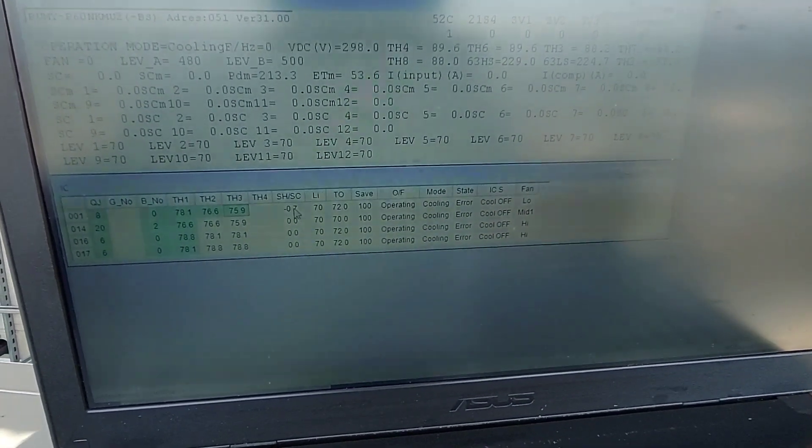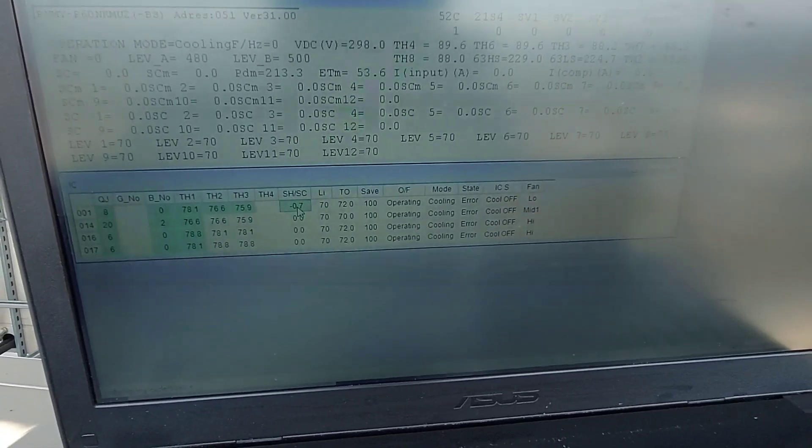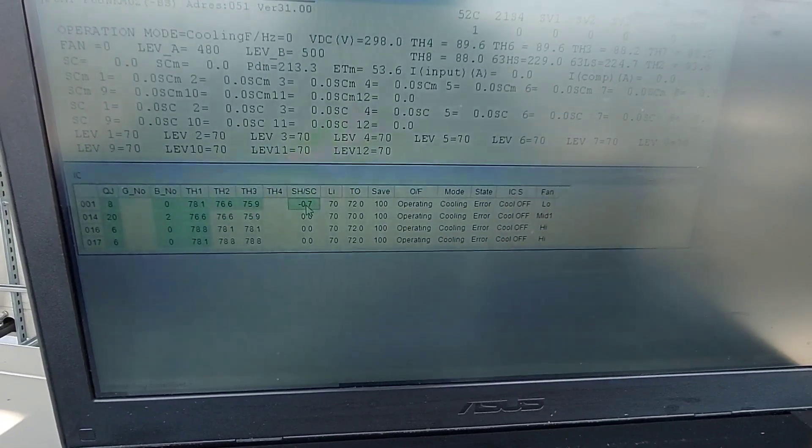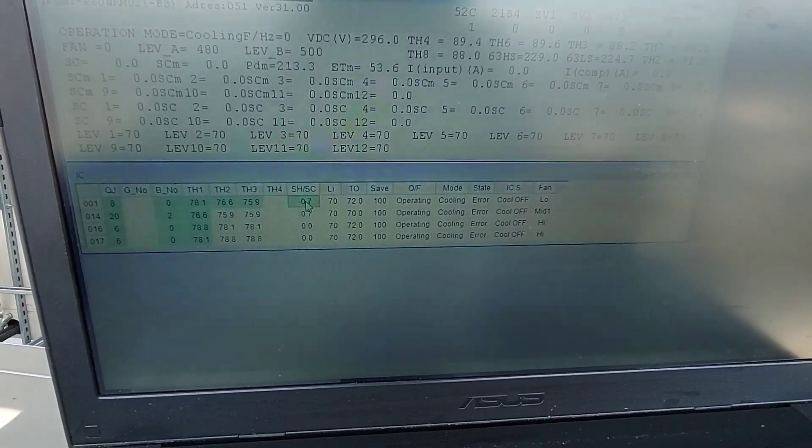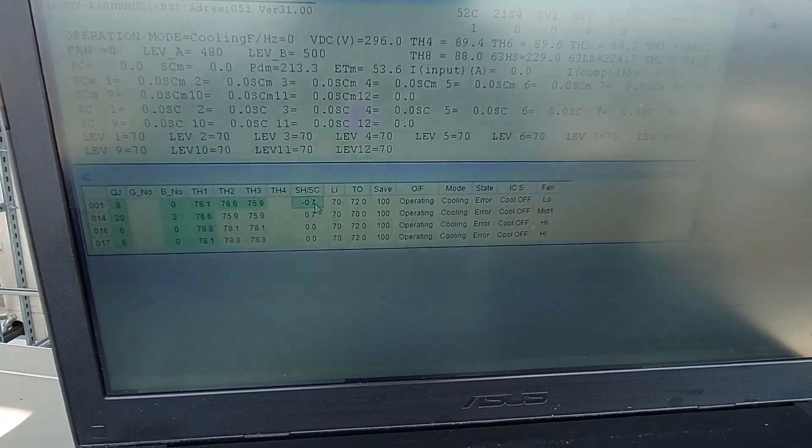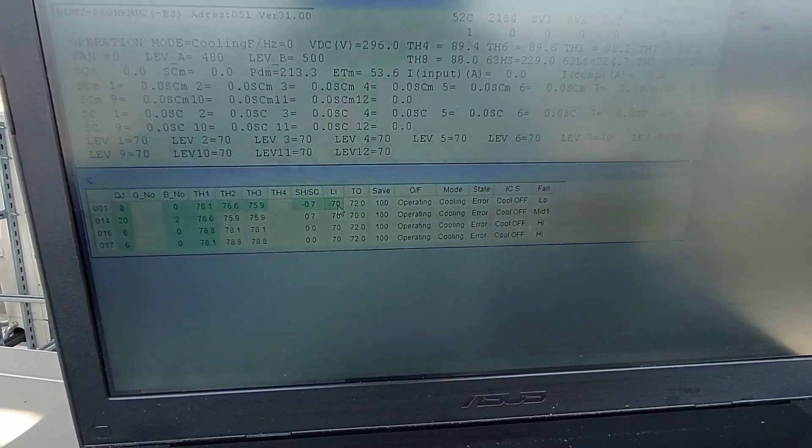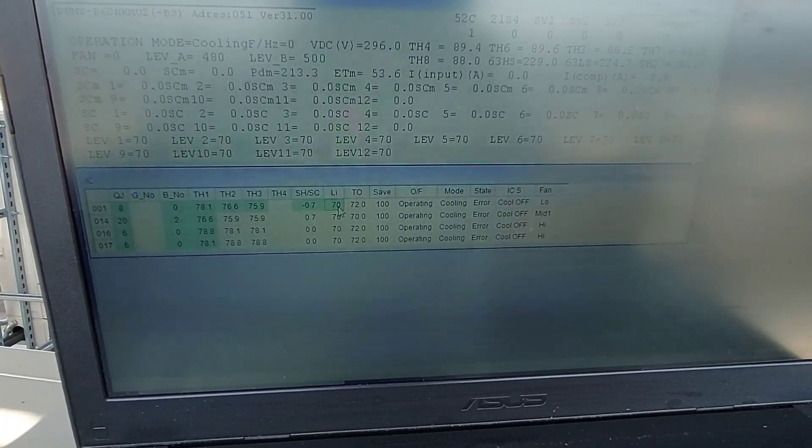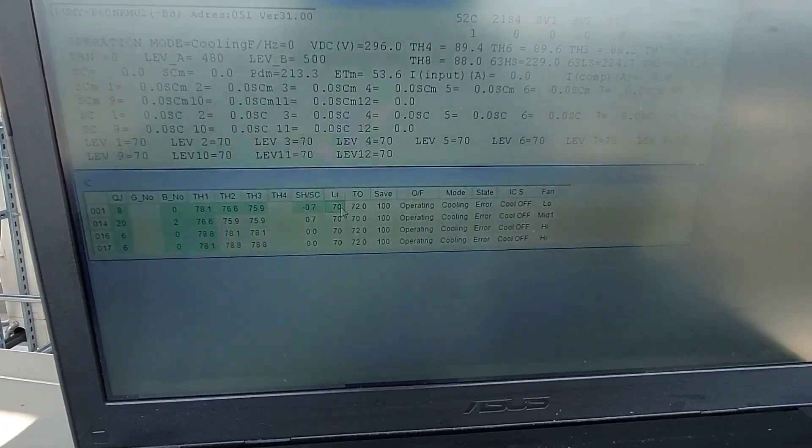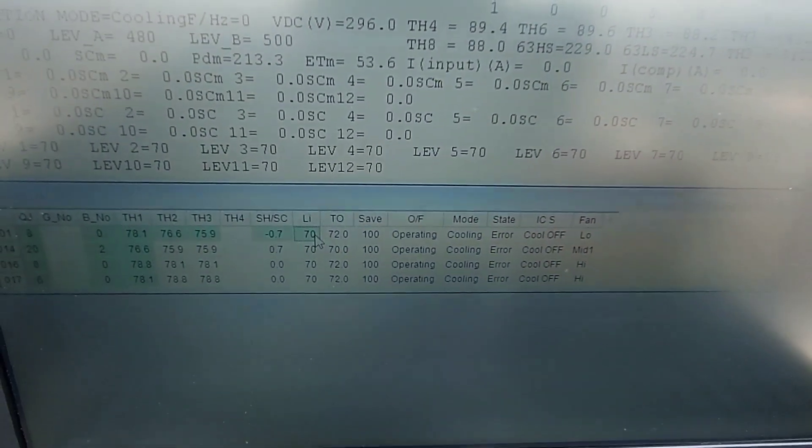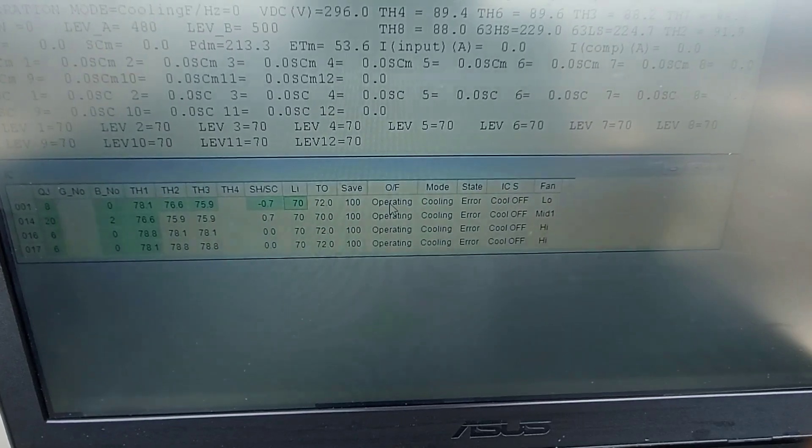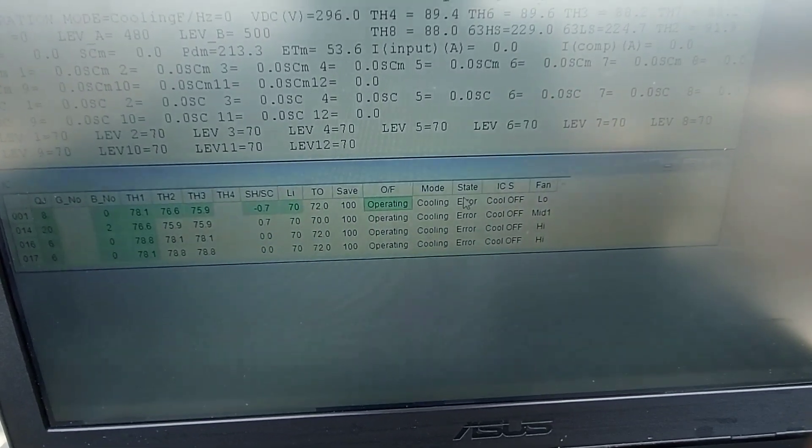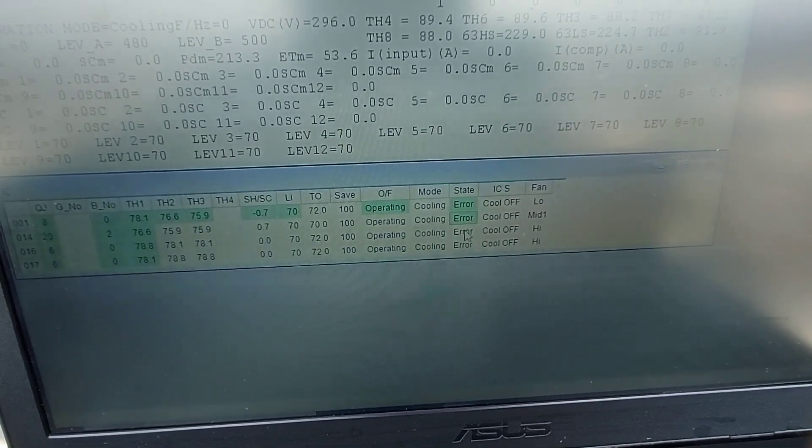TH3 is evaporator outlet. Obviously the difference between the two, whether you're in heating or cooling mode, is going to give you superheat or subcooling. LEV status, it's pretty much closed right now, it's at 70 pulses. Unit is operating cooling error, so I don't even think I could turn this thing on because it's an error. Let's try, let's give it a shot.